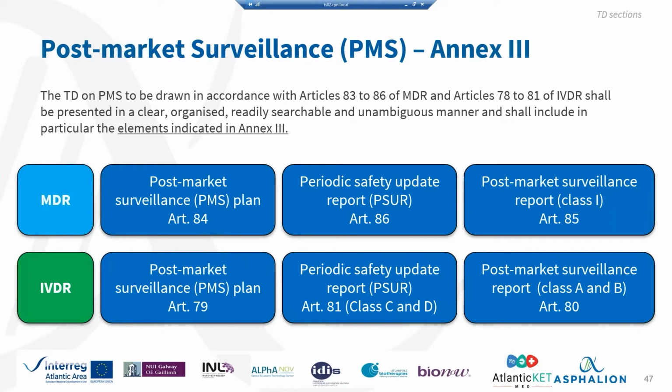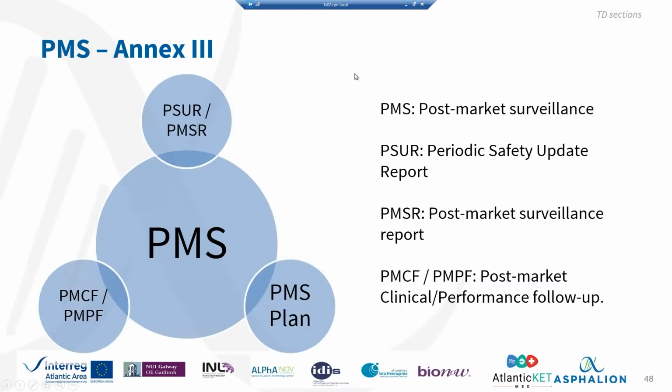In a similar way, we've got the same in the in vitro diagnostic regulation. Okay, we've got the post-market surveillance plan, and then we've got the PSUR for class C and D devices, and then we've got the post-market surveillance report for class A and B devices. Okay. It's important for you, if you're working with medical devices or in vitro diagnostic devices, to familiarize yourself with these terms. Okay, the PMS is the post-market surveillance. Then we've got PSUR, which is periodic safety update report. PMSR, post-market surveillance report, and PMCF, PMPF, which are post-market clinical or performance follow-ups.